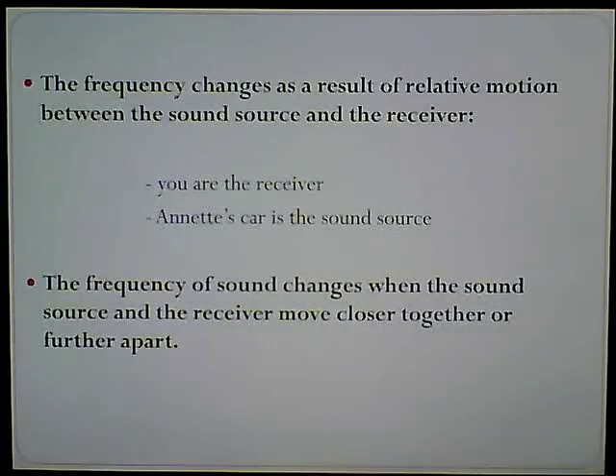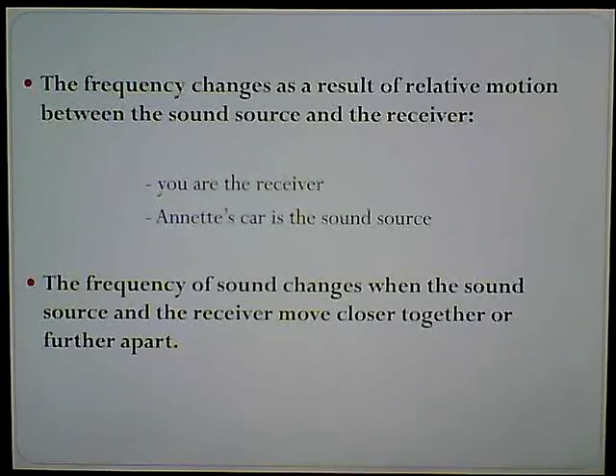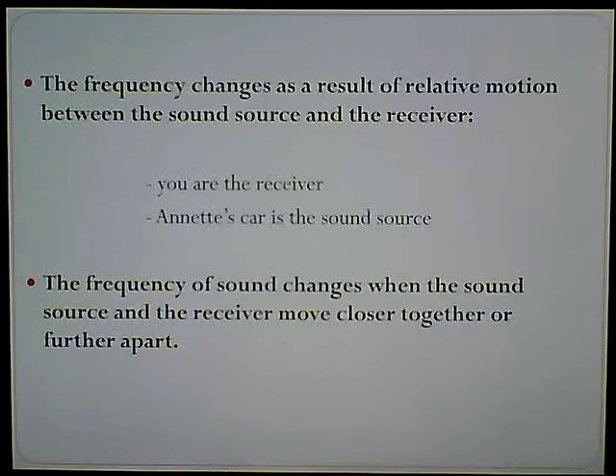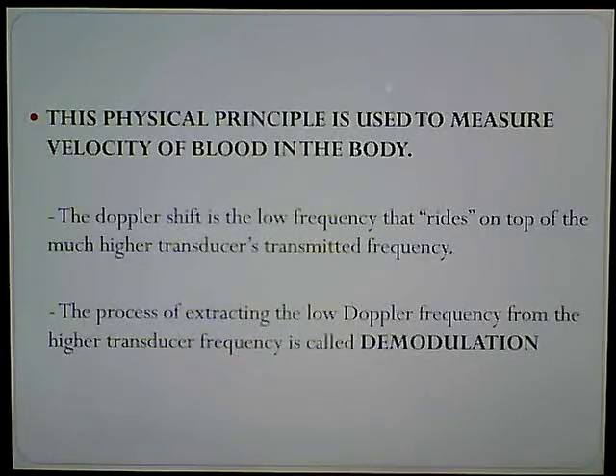The frequency changes as a result of relative motion between the sound source and the receiver. You, standing on the corner, are the receiver. Annette's car is the sound source. The frequency of sound changes when the sound source and the receiver move closer or further apart. If you're standing still — which would be our transducer — the blood cells or Annette's car coming towards you versus going away from you, that's the signal we're hearing. The Doppler shift is the low frequency that rides on top of the much higher transducer's transmitted frequency.